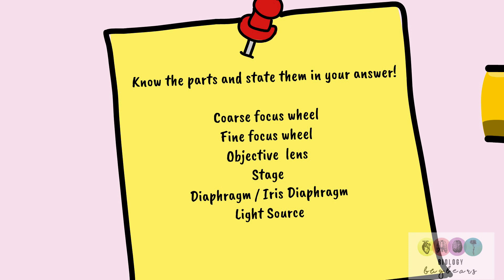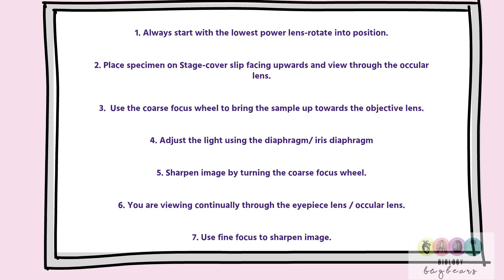Always start with the lowest power lens — just click or rotate it into position. Place your specimen on the stage with the cover slip facing upwards and look through the ocular lens. Use the coarse focus wheel to bring the sample up towards the objective lens. Adjust the light using the diaphragm or iris diaphragm, then use the coarse focus wheel to sharpen the image while looking through the ocular lens or eyepiece, and finally use the fine focus to sharpen the picture.